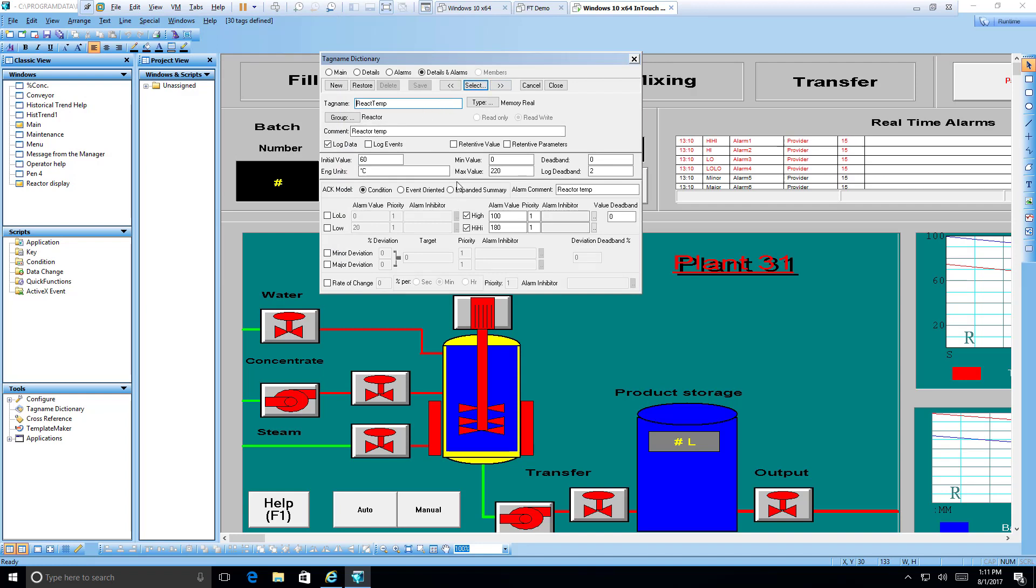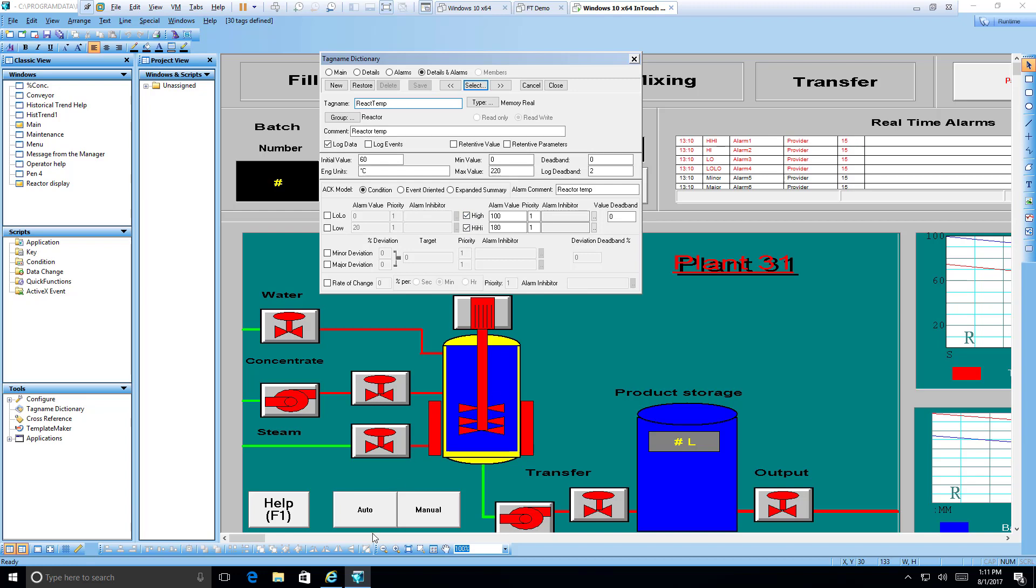Here we go. Reactor level, reactor temp. That's the one right here. So we selected that. We can now see it. And now we see a few things about it. It has an initial value of 60. It has a maximum value. And here we go. What we're looking for right here is the alarms associated with it. InTouch allows you to specify level alarms of low, low, low, high, and high, high. It also allows you to specify deviation of alarms of minor and major deviations. And also rate of change alarms. So we'll keep in mind that for this certain tag, reactor temp, we have a high and a high, high alarm. And nothing else to worry about.